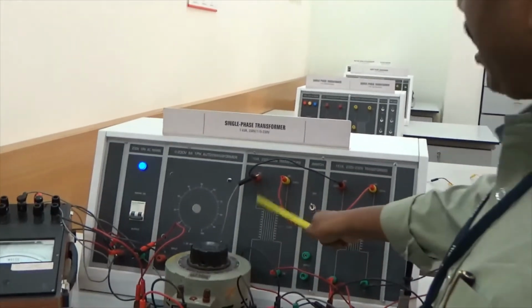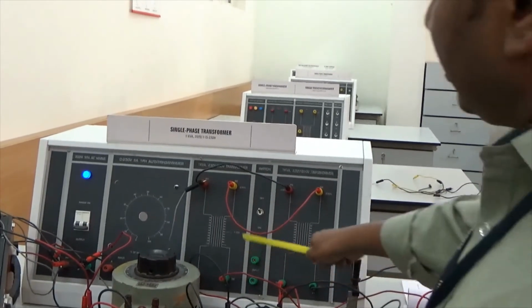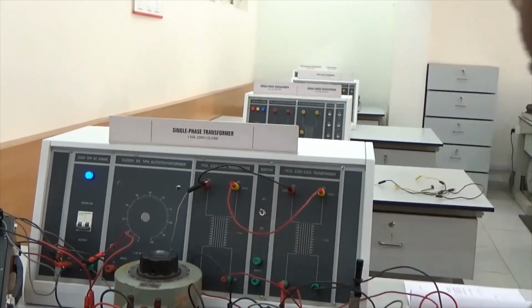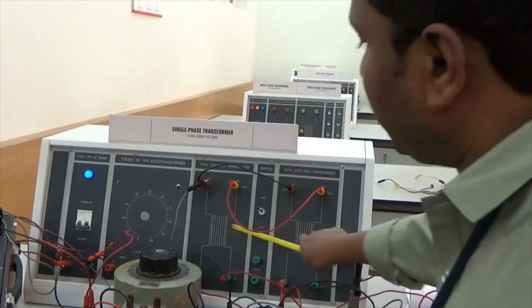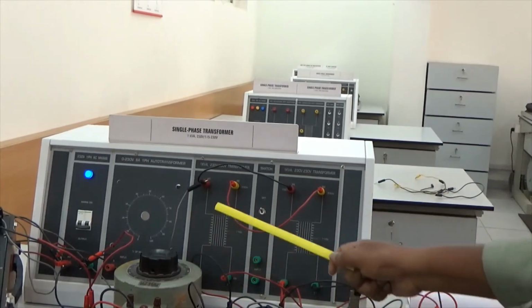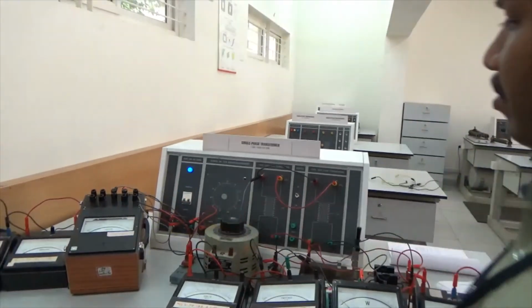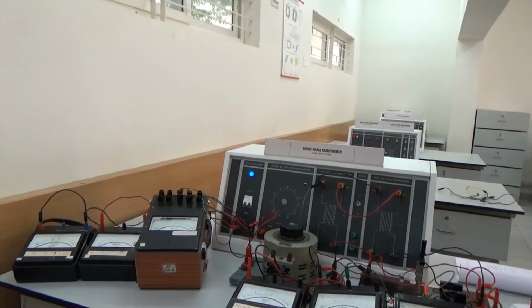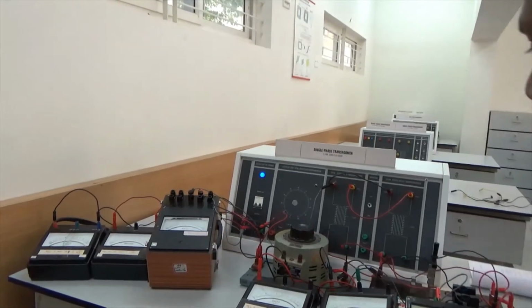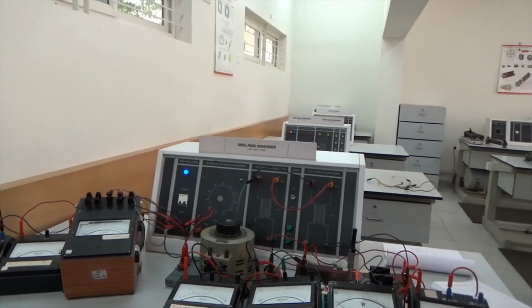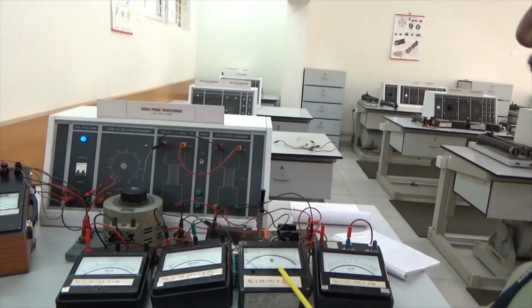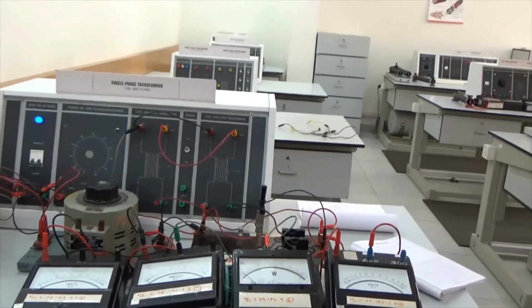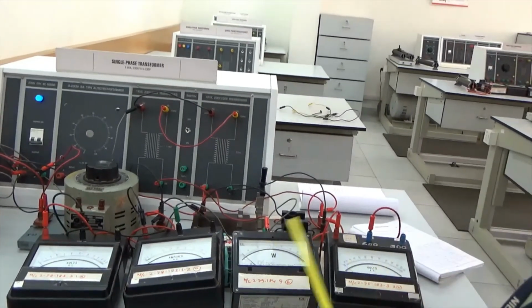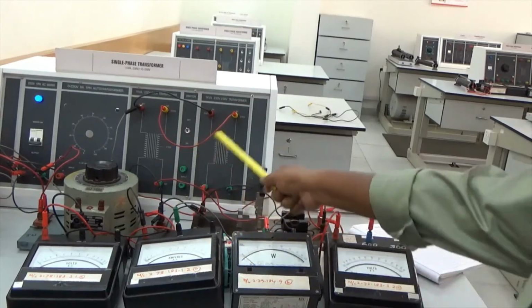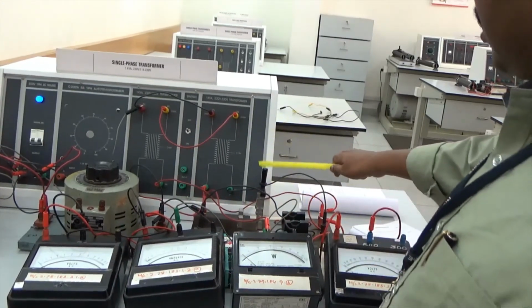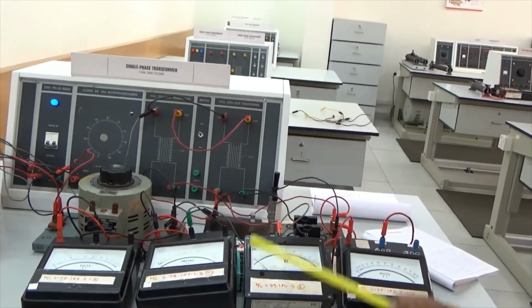Both the transformers, the primaries are connected in parallel, and the secondaries of the two transformers are connected in series. There is a wattmeter connected across the supply and the primary of the first transformer to measure the iron losses of the whole set, and one more wattmeter is connected to measure the copper losses after the short circuit test in Sumpner's test. Various meters are connected to measure the voltage and the current in each circuit path.